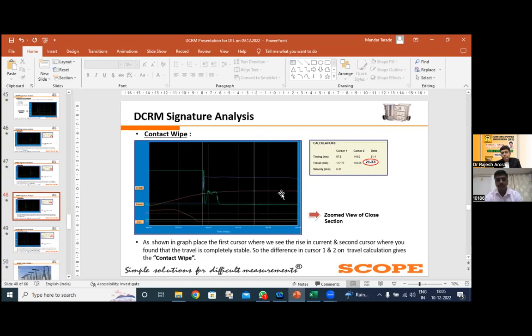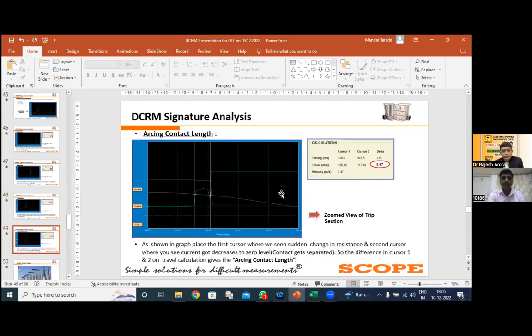Moving to the next point, the contact wipe. Contact wipe is a very important parameter. You need to keep the first contact touching point as it is, and the second point is the mechanism rested point, or the travel stabilization point. The delta between these two points gives you the idea of the contact wipe. One more important thing is that the total travel is the contact gap plus the contact wipe. So with the help of this, you can cross-check the things. I hope this is clear to all. This is very important actually.